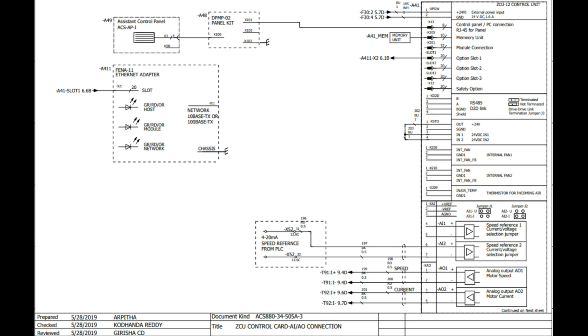And in the center you can see there is a 4 to 20 milliamps speed reference from the PLC. The PLC will give the command for how much speed the drive has to run, according to the PID control or according to the operation requirement. And this is speed reference 2. We can also use speed reference 1, and for that we have to select the jumpers. On the upside of the speed reference, you can see the jumpers. Whether it has to be voltage control or current control, we have to select the jumpers accordingly. Okay, so speed reference is done.